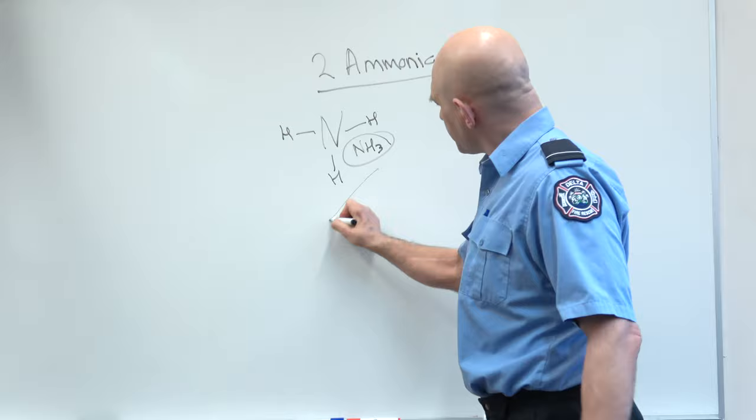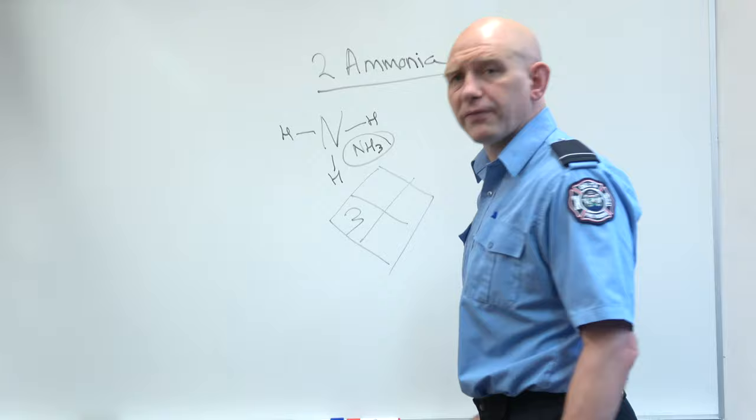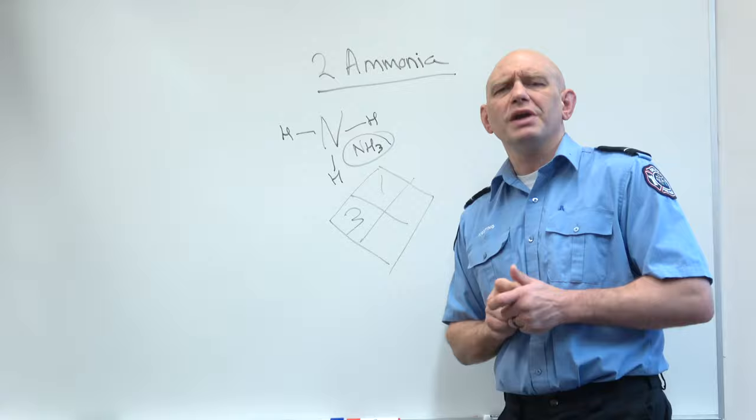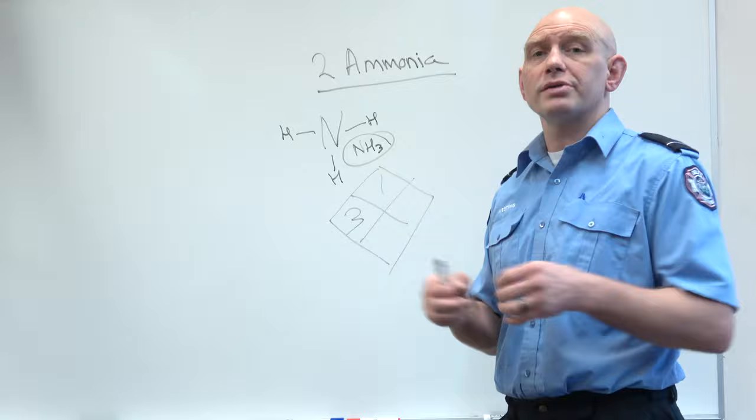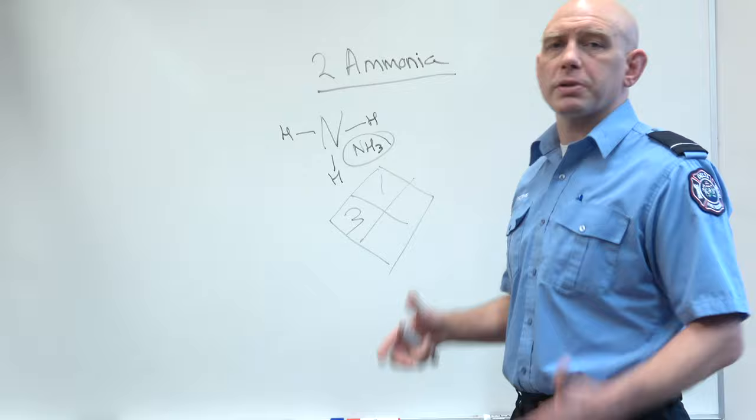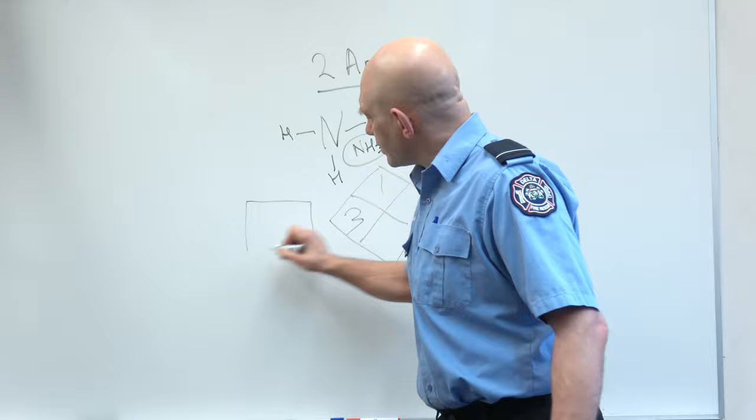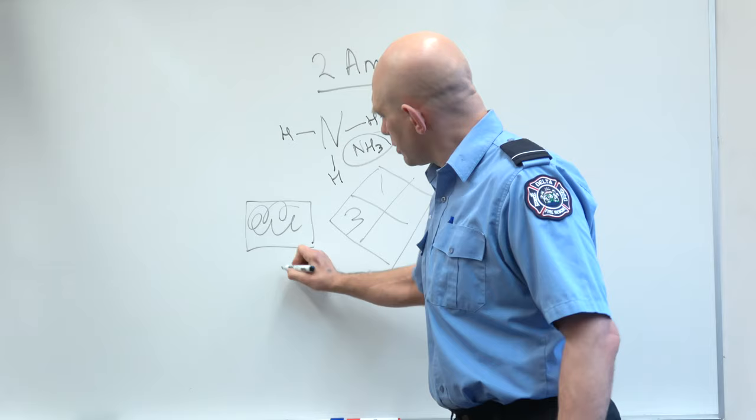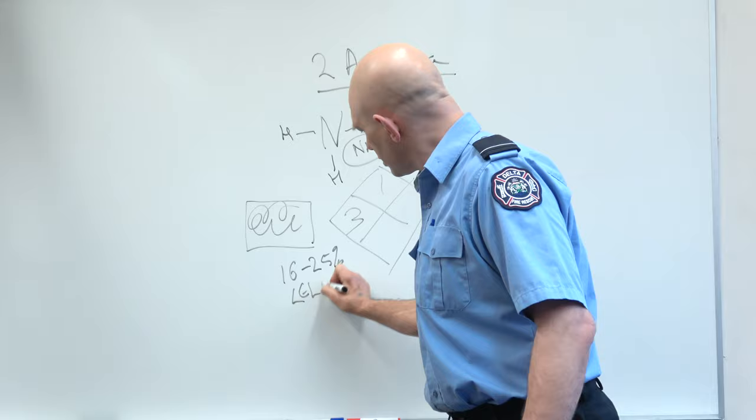This is not the household spray ammonia. That's ammonia gas dissolved in water. We're talking about pure ammonia, 100% ammonia in a vat, say like a propane sized cylinder. Shake it around. If you could open it up without releasing it all, there would be something in there that looked kind of like water. And then the top of it would be vapor. That vapor to liquid transition is what allows it to be such a good refrigerant. The NFPA 704 symbol for ammonia gives it a three for health, which means pretty damn poisonous, and a one for flammability.